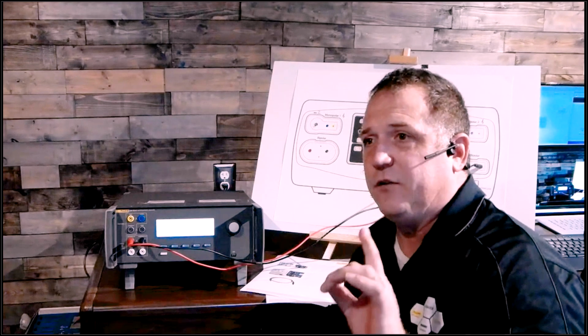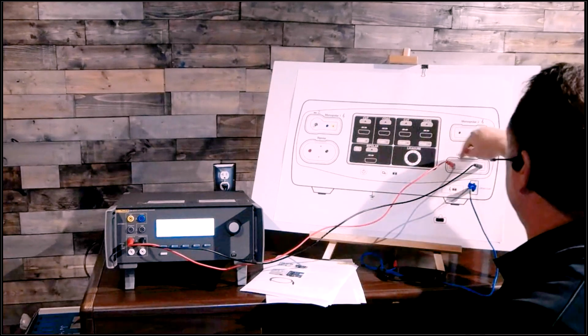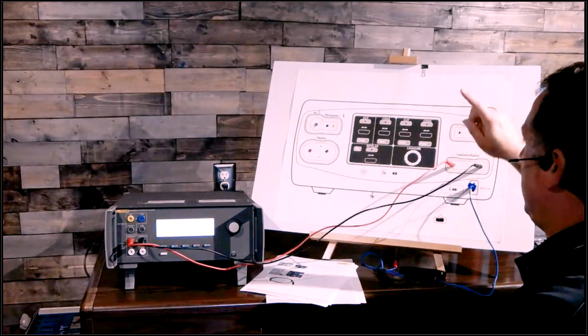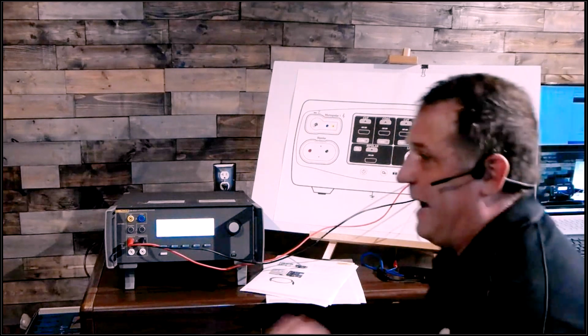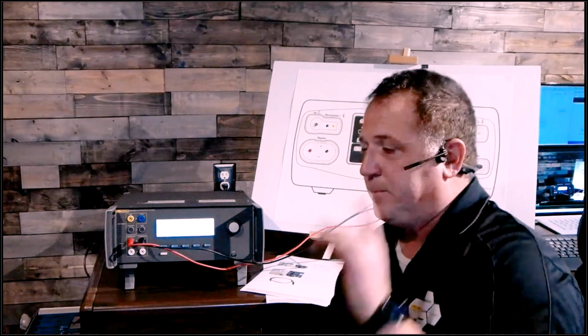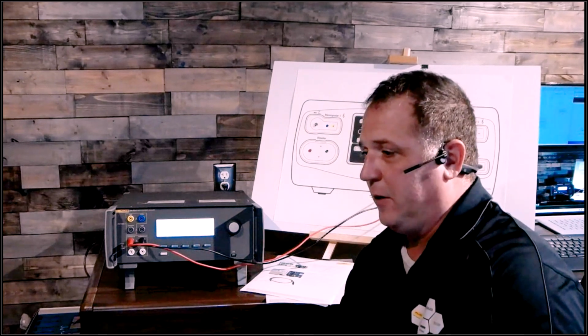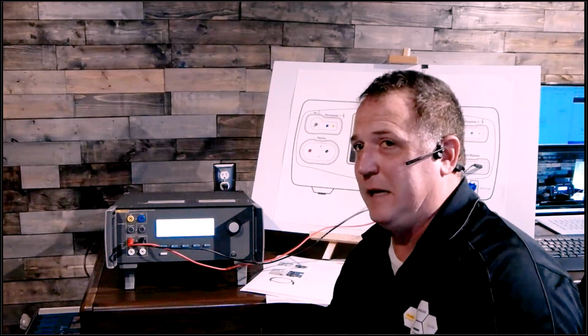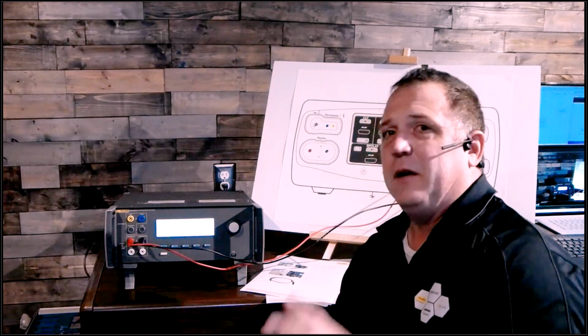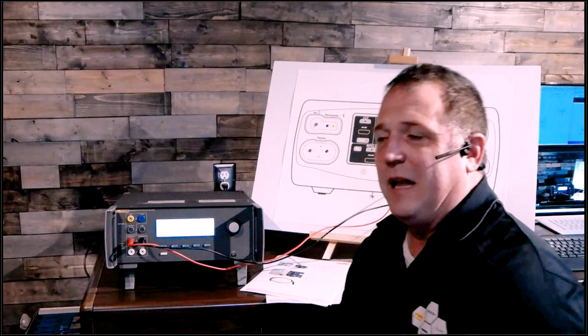Now on your ESU, there are different pencils with different energy ranges, so it's not going to recognize this. We have to go into service mode. I'm not allowed to tell you the service code, read your service manual, it's in there. Get into service mode and go to the RF energy output tests.